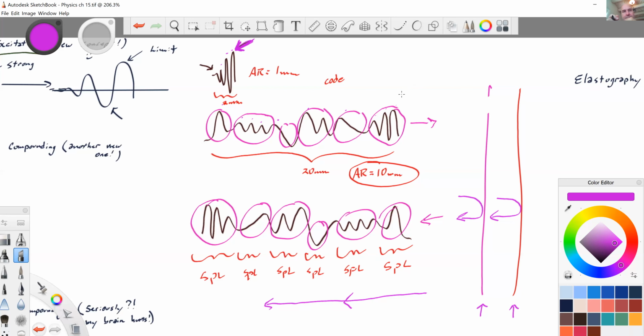We'll explain that soon enough. Just know that peak intensity and especially that peak rarefaction are dangerous, so you don't want to go beyond a certain point there. But by creating a much longer pulse, never exceeding that peak, you can keep it safe for the patient. Coded excitation occurs in the pulser with codes and special mathematical techniques. Along with the pulses, high quality coding of the excitation improves resolution. I don't know how it does that, but it does because that's what it says.